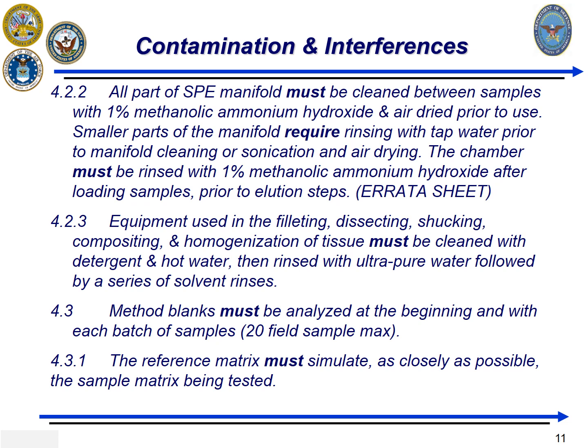This is the big change. Previously, it required sonication. Now it's stating that sonication may be used. Smaller parts like the needles, adapters, reservoirs, and stopcocks associated with the manifold require rinsing with tap water prior to manual cleaning or this sonication and air drying.